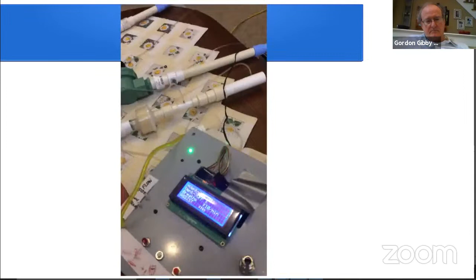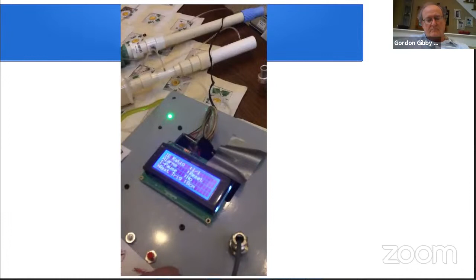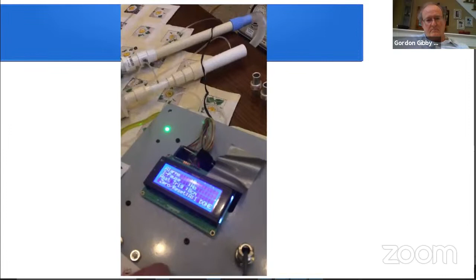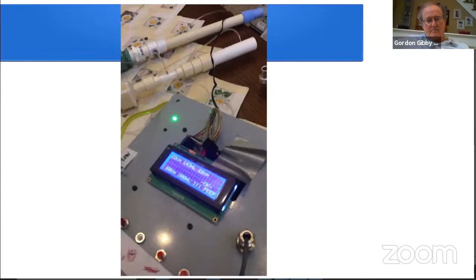If I hit the menu button, then I immediately go into a menu system, and I can go down through menus to set pressure limits, end expiratory pressure, volume limits, what's called the I to E ratio. I can change how it ventilates, what duty cycle. I can reset alarms, and then there's a thing way down here to reset the I2C bus, because we were very concerned that we would have problems with the I2C bus. We never did, really, but we built it to be careful about that.